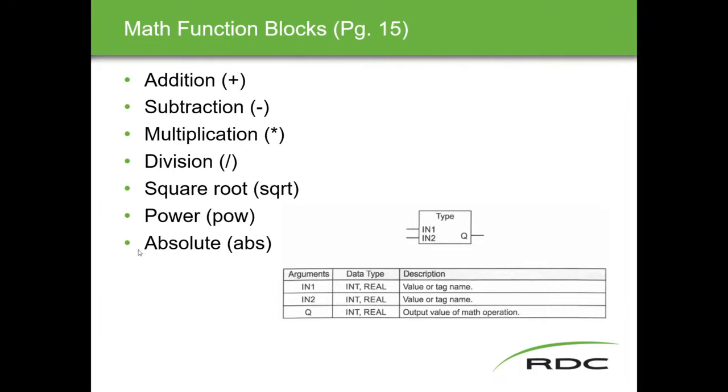Okay, more math function blocks. You can see where we're building up here. This is the exact same way we approached the ladder logic. We started with Boolean, then some comparisons, and then we did some math. So here we are at math. Math function block, again, type name will change: MULT, ADD, SUM, whatever. There's lots of different ones. Values for the inputs will be integer or real, and the output has to be matching. Whatever type of data you have on the left-hand side, you're going to have the same data on the right-hand side, straight across the board. That's probably a programming 101 thing to remember. Then you can put an analog transmitter value in here and get a one or a zero out of here, and vice versa.